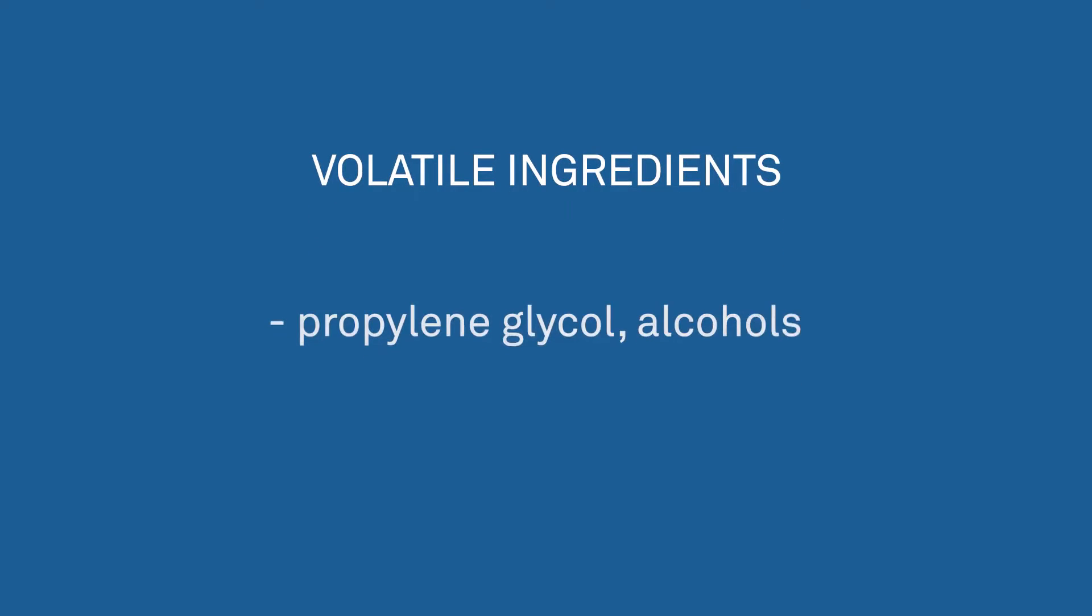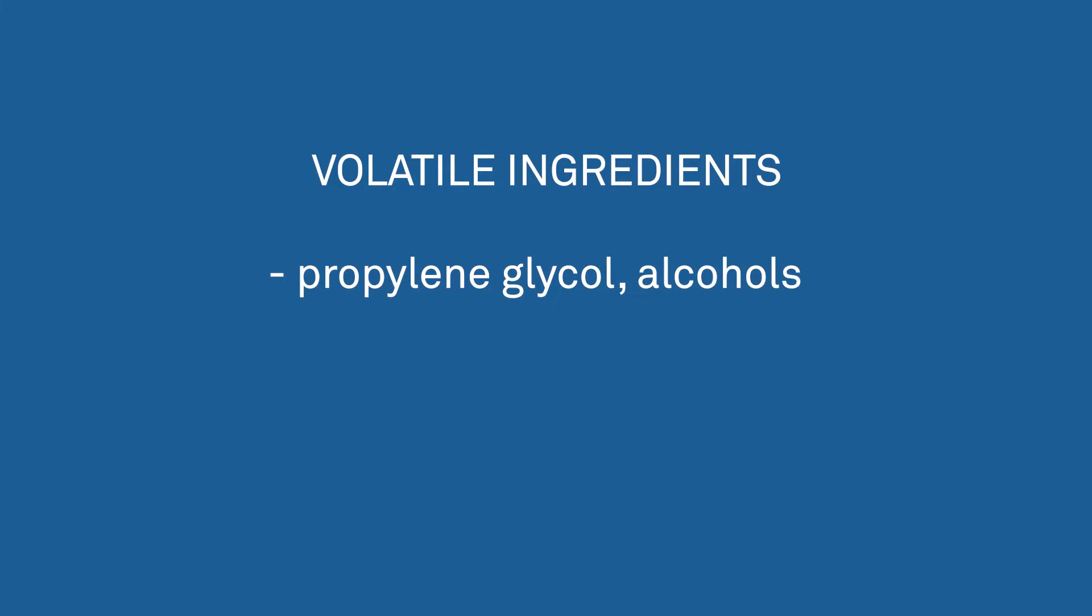There are a few ingredients like propylene glycol and alcohols that can cause issues with the mirror. The problem with these volatile ingredients is that they also condense on the mirror. When we heat the mirror up, they evaporate at a different rate than water, and they interfere with the readings.